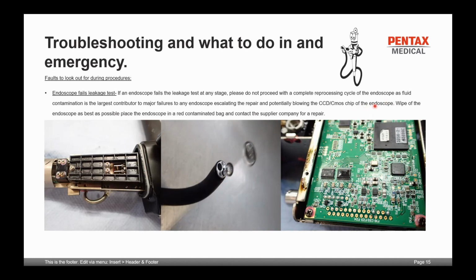If at any stage they do find that the endoscope has a leak, they are to wipe the endoscope off as best as possible, place it in a red contaminated bag, and contact the supply company for a repair. A little example I like to give the CSSD and nurses is that endoscopes have a bending rubber on the distal end, the bending section of the endoscope. And it's a piece of rubber.